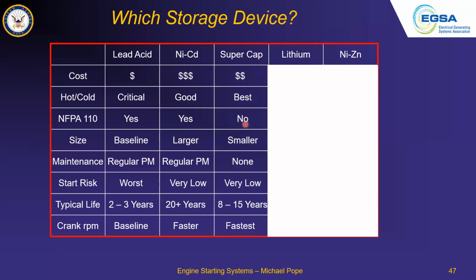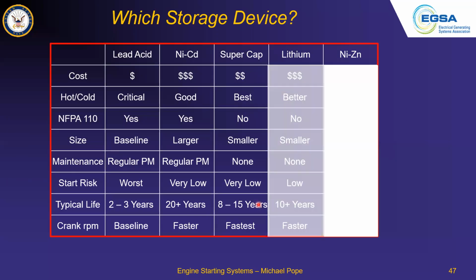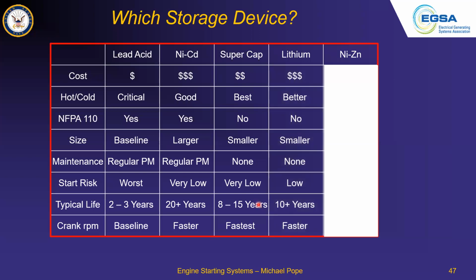Because there's not a chemical reaction, it has the best hot and cold performance. It is not temperature dependent. Does not meet the present NFPA 110, but there are some changes happening there, so it's a case of watch that space. Size, it's smaller, lighter, doesn't need any maintenance at all. Start risk is very low, and we reckon the life of that is between 8 and 15 years. Fastest cranking RPM. Lithium batteries, and you can see.